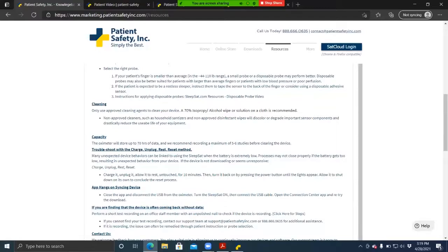A question that we get pretty often is the capacity of the SleepSat. It holds up to 70 hours of data, and depending on how long your patient is sleeping, that has a maximum of 5 to 6 studies before the device needs cleared. Again, we would recommend only sending the device out with no data on it, so it only has one set of patient recordings on it at a time.